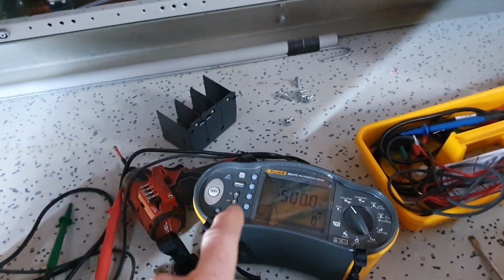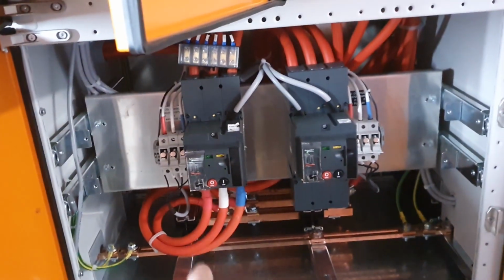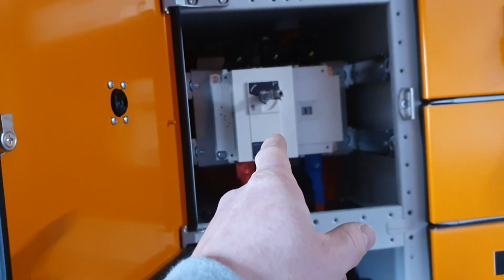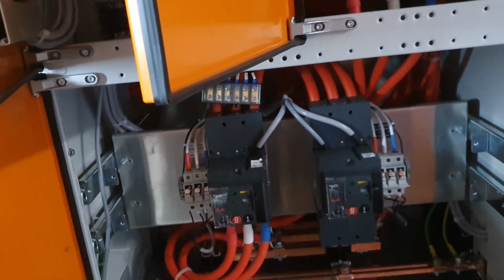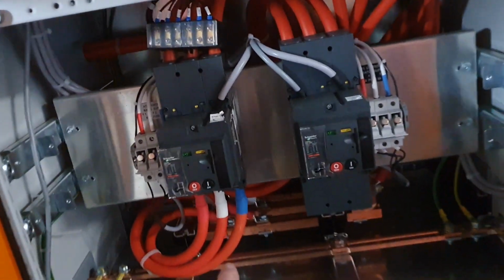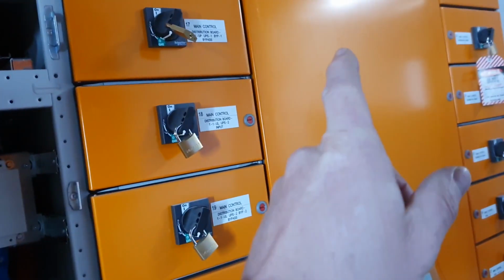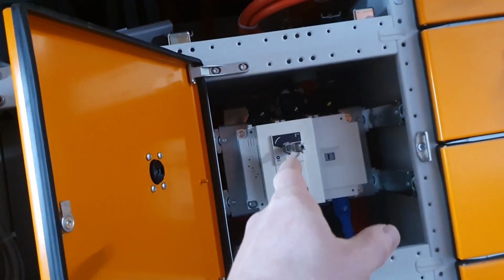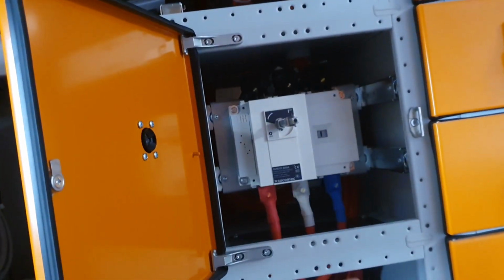So that's fine. Basically what I've done is a megger test on the outgoing side of this. I've turned this switch on, which powers that, but because this is isolated here, I can safely test from the bottom here, through the bars, up through this switch and all the bus bars in that section. So I'm happy to turn this on now, and I can turn that on as well because I've tested through, okay?